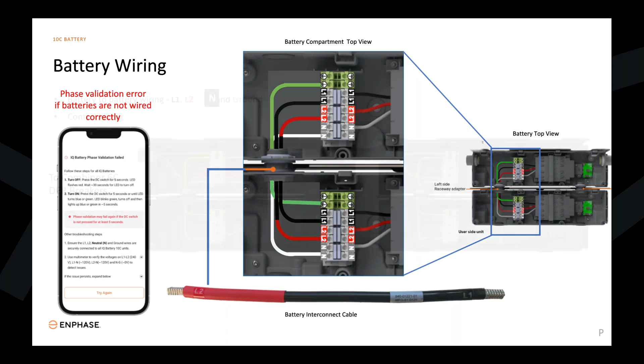When we're wiring multiple 10Cs, Jarrett, it's a little different than the subunits, isn't it? So what do we have here? Yeah, essentially in this one we have two 10C batteries, and coming from your combiner box on the left, we have line 1, line 2, a neutral, and a ground coming into that wall-side battery. Then the wall-side battery gets wired into the user-side subunit, and again we're going to swap our phases there.